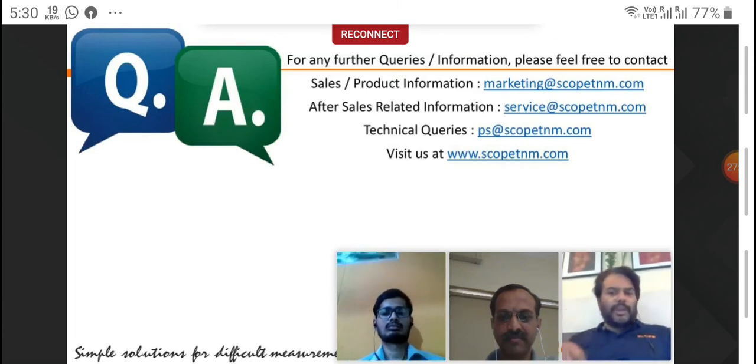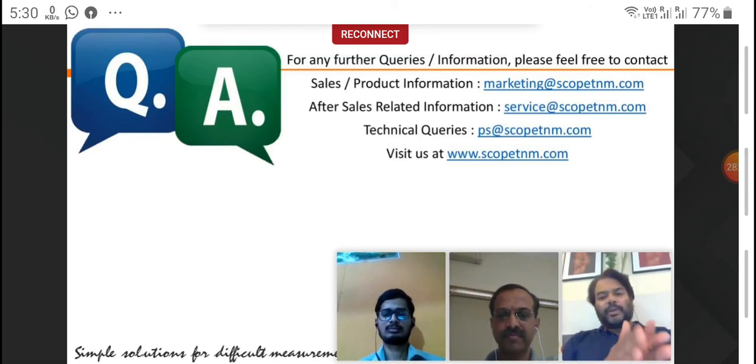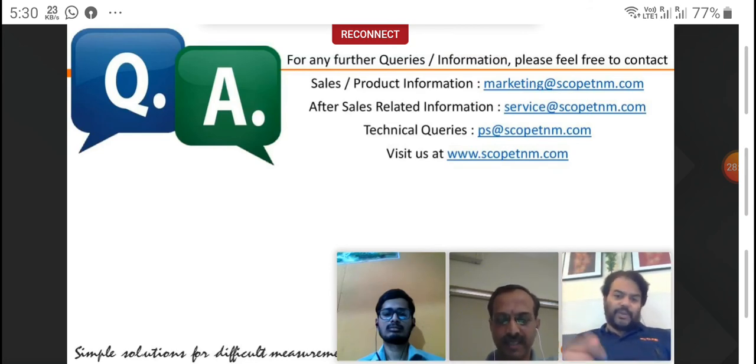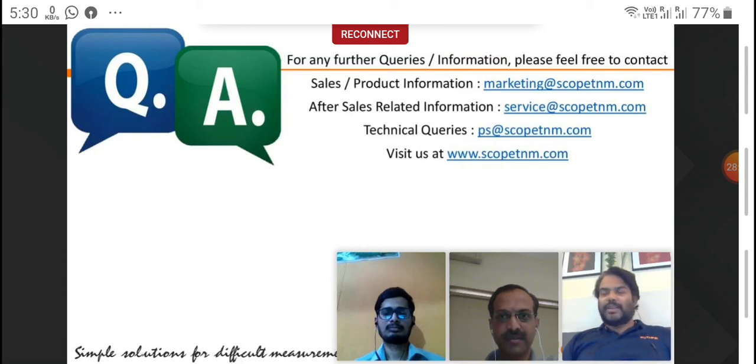So in short, Mahesh, what you are saying is that in the TDR, we will first get multiple signatures, as shown by Vishal during the presentation. We have to start from the first or the nearest fault, which will be considered the most severe fault. We repair that one first, then retest, and one by one we will attack the faults. Yes, that is true. That is the process you are trying to tell. Yes. Okay.